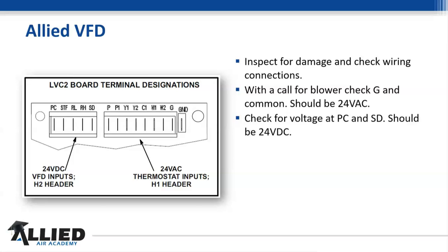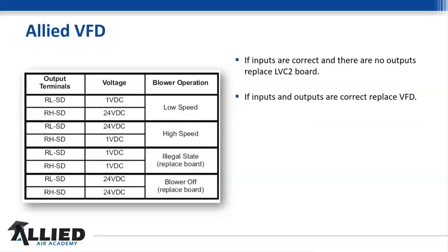But there's also one other check that I would like to do before we say we're good to go. We got this. This is a really important piece of paperwork to have right here. This tells you what the board should be putting out at low speed, high speed, illegal state. I love that one. I understand that one. And then blower off. And if you're getting these readings on here and you bypass your VFD drive and your motor works, and we've ohmed it out, we've done all of our other homework on here, and everything else runs, this tells you whether your drive is bad or whether your board is bad.